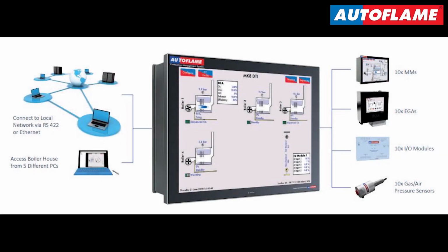The Mark 8 DTI is the data transfer interface. This is a communication gateway that allows remote monitoring and control of your boiler room. Up to 10 MMs, 10 EGAs, 10 gas and air pressure sensors, and 10 input output modules, which are used to interface third-party equipment, can be integrated with a single Mark 8 DTI.